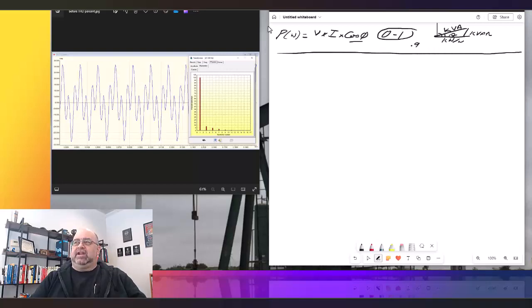Now we know that my fundamental here is actually not 60 hertz. If this had come up, hit the peak, and come down again, that would be 60 hertz. But because I have such high triplen, or third harmonic, content, it actually shows on my meter as 180 hertz. So this fundamental is not 60 hertz — that's actually my third harmonic.